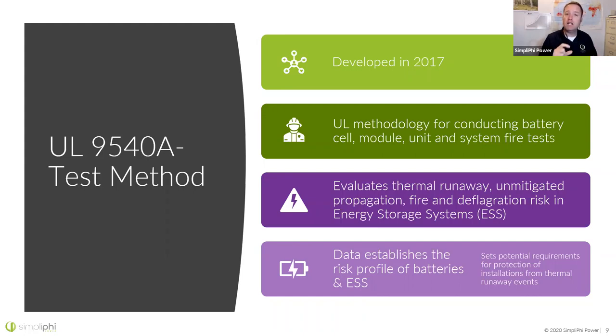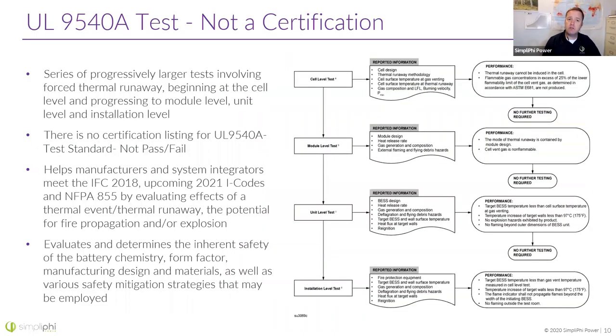So what's setting us apart is kind of common now, with lithium ion chemistry - I see a lot of them going over to lithium iron phosphate. But let's take a look at the way people package these things, the form factors, and the larger battery modules. UL9540A, developed in 2017, is the methodology to conduct battery cell, module, unit, and system fire tests. The system fire test incorporates other fire suppression systems like sprinklers, built-in fire extinguishers, or deflagration radiuses. This test method establishes a risk profile for the battery and energy storage system, which dictates our 9540A listing and what's called out in our instruction manuals.